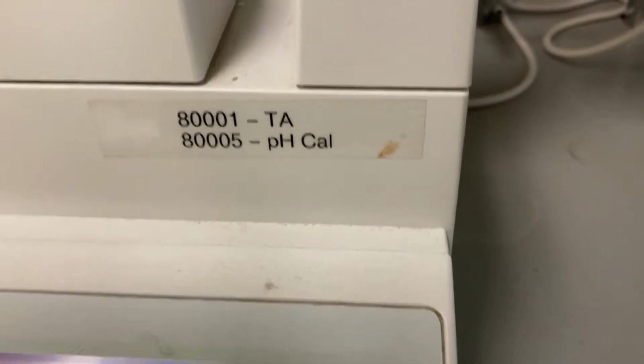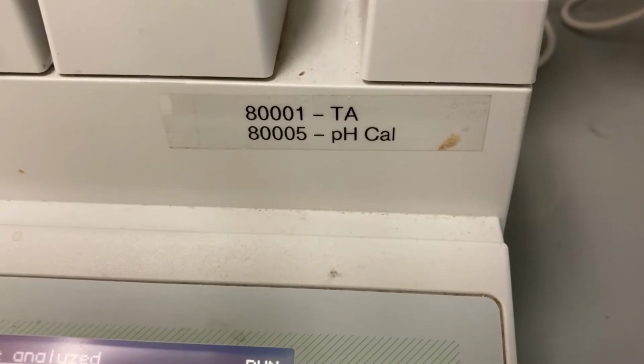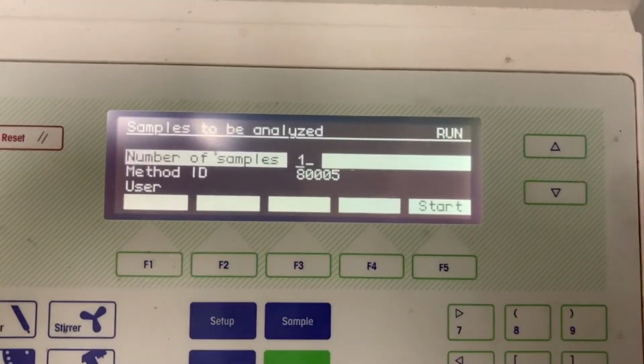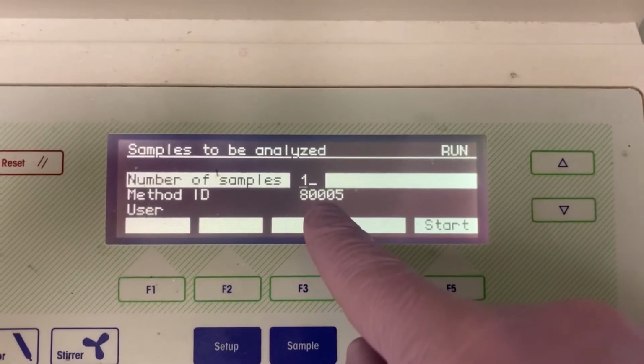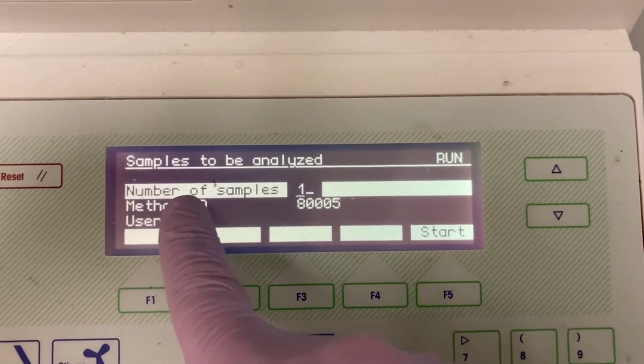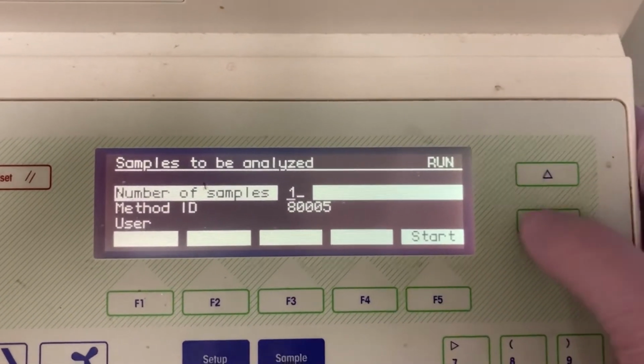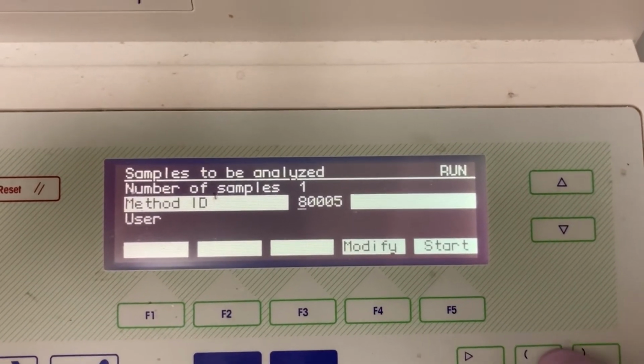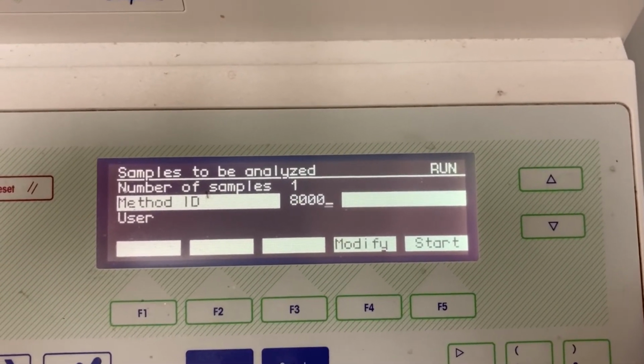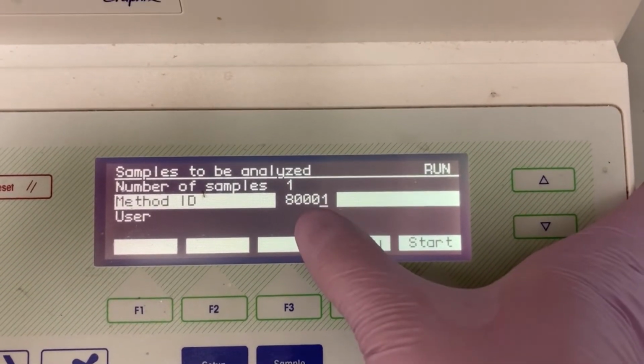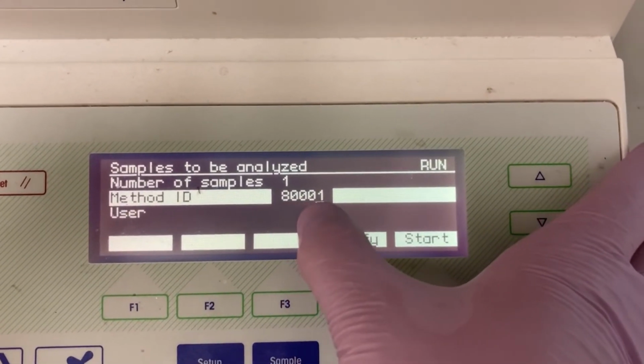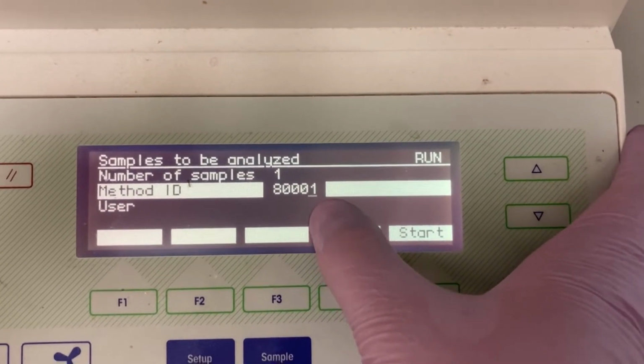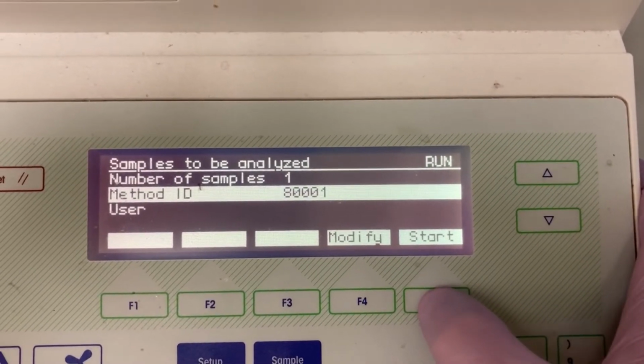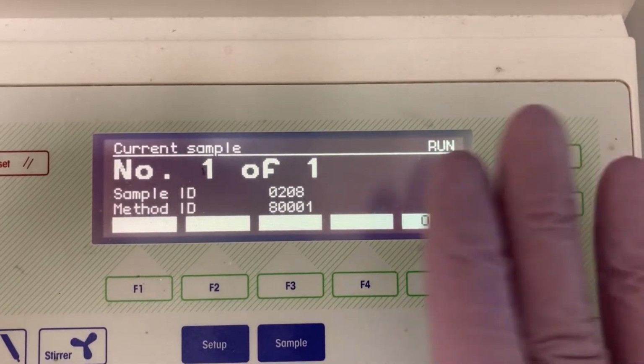So, as you can see on this sticker for TA, the method should be 80001. And we're going to do one sample at a time. So, you want that to stay as one. So, once you've changed the method ID to 80001, you hit start. And now it's ready for the sample.